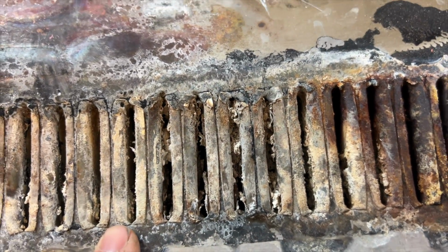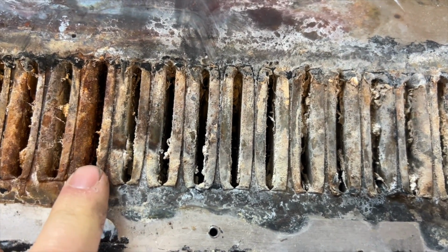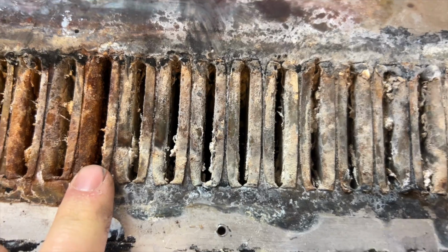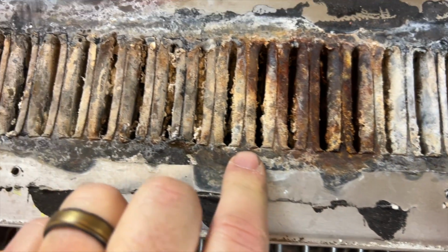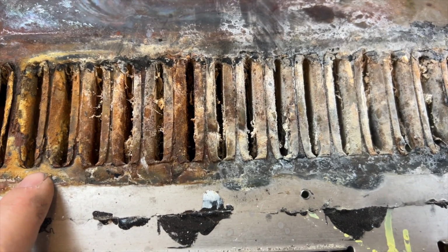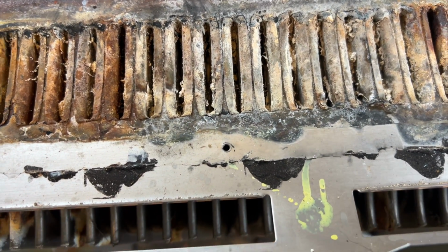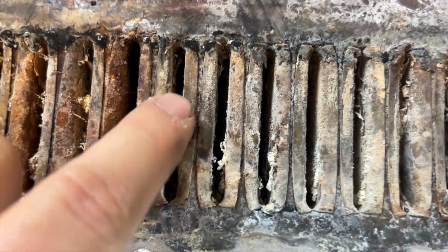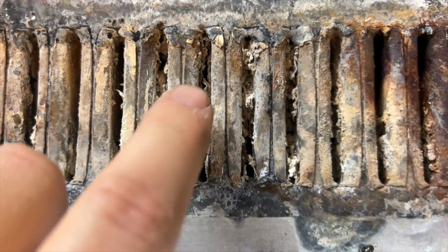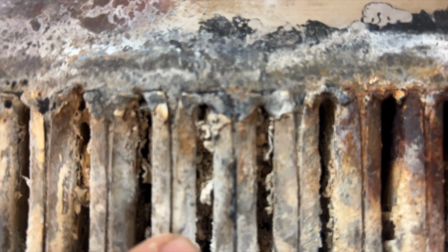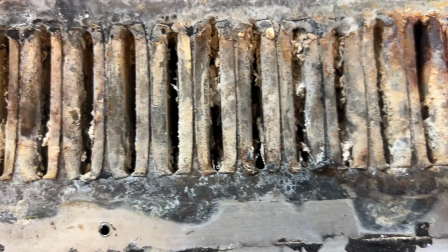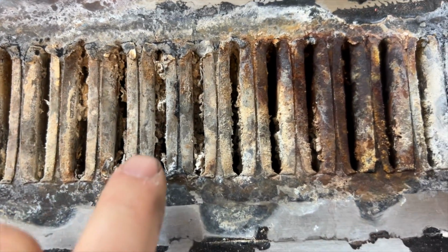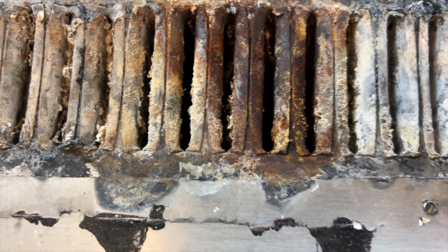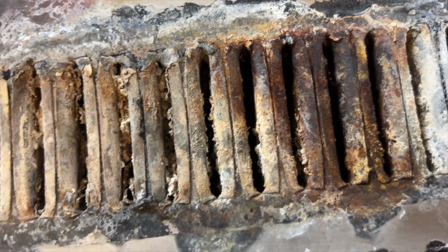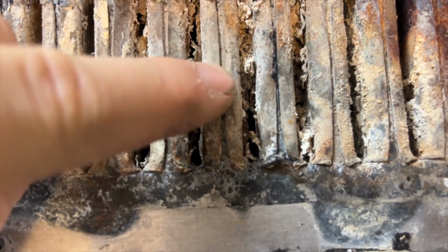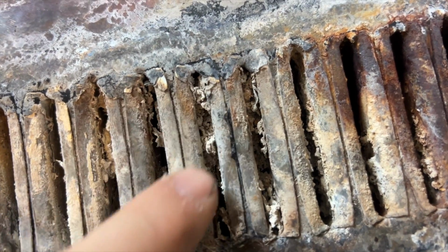This was not commissioned. The gas pressure was off, which means your fuel to air mixture was not proper, which gives us improper combustion. We still have combustion, but not proper. So it's dirty combustion. You get a lot of nasty stuff like sulfur dioxide and a bunch of other nasty stuff. Now think about all that stuff just sitting in water, and you can see that these little holes here, they're pretty thin. So as this started to deteriorate, all that stuff starts to plug it up. So the problem with this one is we had severe rollout, and what happened was the secondary heat exchanger was completely plugged. So it had stoppage, and this is why this is a bad design, because these holes here are so small. At least with the regular one, it's a big tube, so it's not going to plug up.